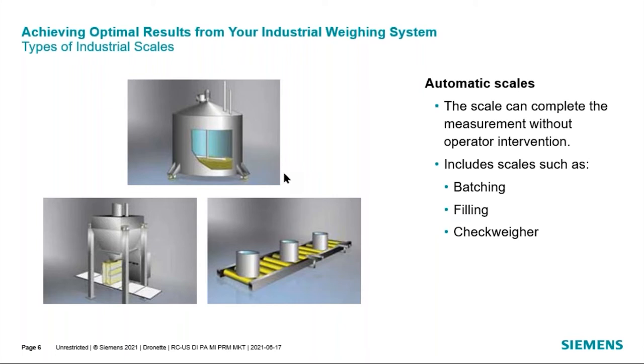With a gain-in-weight system, the mixer bin is placed on load cells and it monitors as each component is added, stopping the material transfer when the desired set point is reached. Filling machines fill containers — bags or bottles of material. A scale is installed underneath the filling station with controls built in to transfer the container onto the scale, start the material flow, stop it when the set point is reached, and then index to the next container.